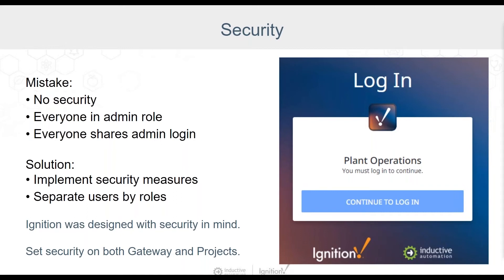The first mistake we often see in security is leaving security settings at the default — and in some cases, that means no security, which is a pretty big deal. Security can be set at both the gateway and project levels. By default, the gateway configuration, gateway status, and ability to launch the Ignition Designer are all restricted to the internal admin role, so some security is in place already. However, it's good practice to review these settings in your environment.